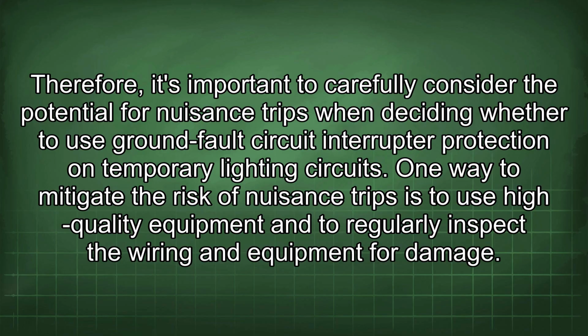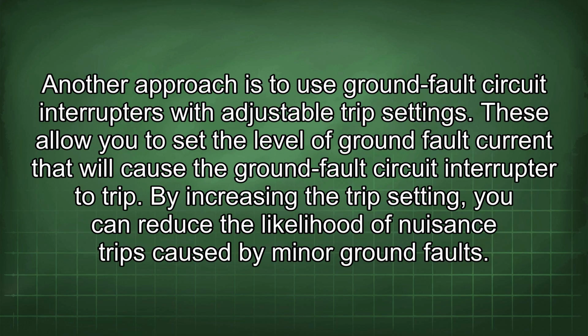One way to mitigate the risk of nuisance trips is to use high-quality equipment and to regularly inspect the wiring and equipment for damage. Another approach is to use ground fault circuit interrupters with adjustable trip settings. These allow you to set the level of ground fault current that will cause the ground fault circuit interrupter to trip. By increasing the trip setting, you can reduce the likelihood of nuisance trips caused by minor ground faults.